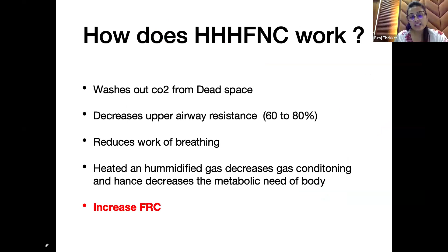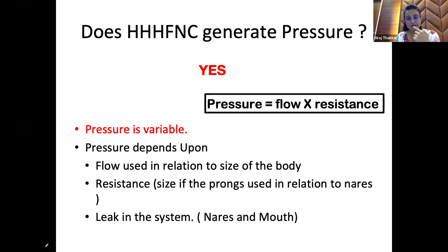Yes, it can. It's again a simple physics principle. If any flow is passing through a tube and there is a resistance applied to that tube, definitely there is a generation of pressure. So in HFNC also, there is a flow which is being obstructed and there will be a generation of pressure. But the pressure generated here is variable. It depends upon how much flow you're using. It depends upon how much resistance is being applied in the form of the size of the prong used in relation to the nares. And it also depends upon the leak in the system, that is around the prong in the nares and from the mouth.